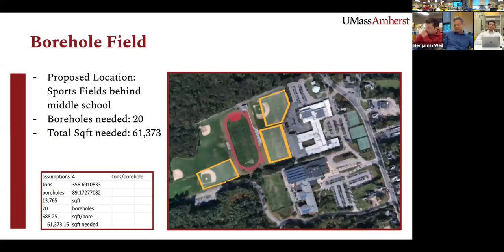Assuming that we're gonna use 4-ton boreholes, you'll need about 20 boreholes, which would require roughly 61,000 square feet. And you can see on the figure on the right, we proposed 3 different locations behind the middle school that this could potentially work. And we did study the middle school, but by making the field bigger, you could also tie it into the school if that's something you guys would like to pursue in the future.